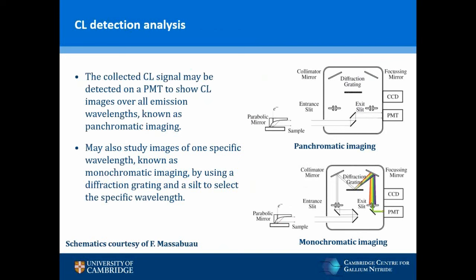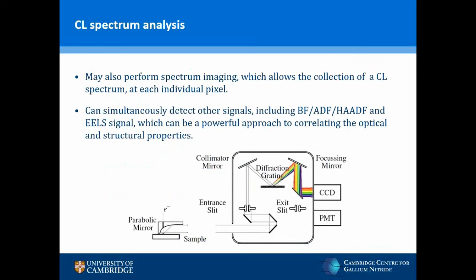The cathodoluminescent signal may be directly detected on a photomultiplier tube to give a CL intensity image over all emission wavelengths — known as panchromatic imaging. The CL intensity image may also reflect just one emission wavelength, known as monochromatic imaging, by using a diffraction grating to disperse the light and a slit to select the desired wavelength. The CL spectrum may also be recorded by dispersing the signal and detecting on a CCD camera, with spectrum images collected over a range of points to provide a 3D dataset. Simultaneously, other signals may be collected, including bright field, annular dark field, high-angle annular dark field STEM signals, as well as the EELS signal.